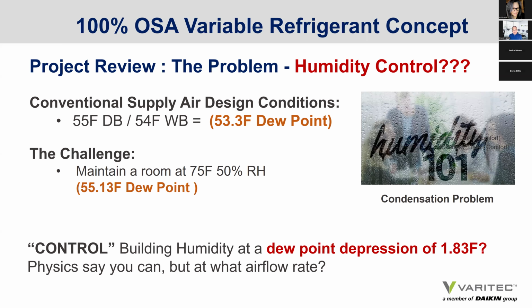And historically, in Phoenix, Arizona, we can say yes. Why? Our buildings leaked. So we needed a lot of air to overcome that 115 degree summer design day, 110 degree design day. And in doing that, we could control the latent component or the humidity component to a room condition of 55 degree dew point. But be aware, if you're providing 55 degrees off the coil and you're maintaining a room condition of 75, 50% RH, the supply air only has a 1.8 degree dew point depression, which means that you can dehumidify if you have enough air. But here's the challenge.